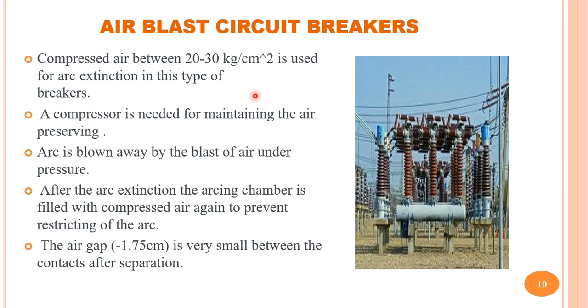The next type of circuit breaker is the air blast circuit breaker. Compressed air between 20 to 30 kg per cm² is used for arc extinction, with a compressor for maintaining air pressure. The arc is blown away by the blast of air under pressure. After arc extinction, the arcing chamber is again filled with compressed air to prevent restriking of the arc. The air gap between contacts after separation is very small — nearly 1.75 cm — which is an advantage, as the arc can be extinguished with a small arc length.